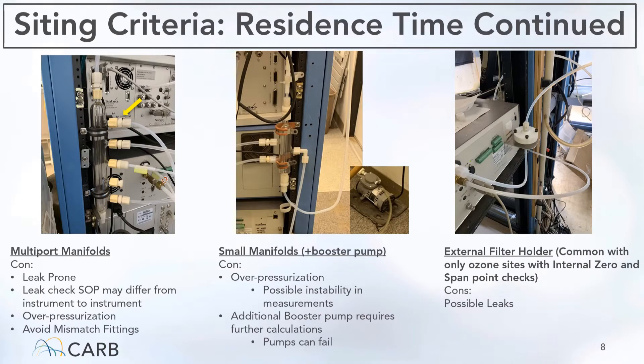Your station manifold plays a key role in your residence time calculation, and the type of manifold you use depends on your sampling goals. For example, if your station needs to sample multiple gas species, you may want to use a multiport manifold shown here to the left. Or if you're focusing on one pollutant such as ozone, you may want to use a smaller manifold, or even without a manifold and just use an external filter holder shown to the right. There are several caveats when using these types of manifolds, especially ones with multiports. One disadvantage is that leaks can occur around the Teflon fittings, and if there are leaks, your residence time will change.